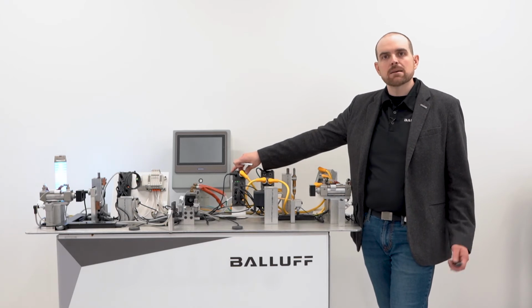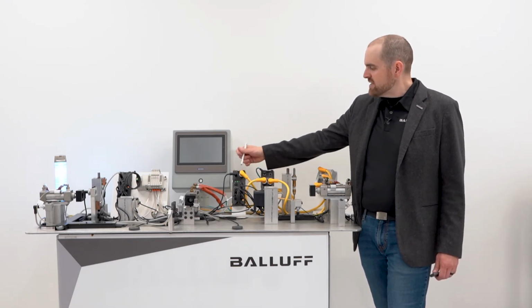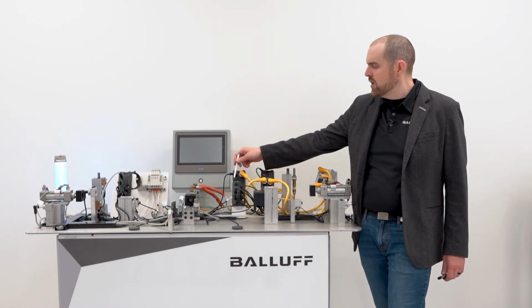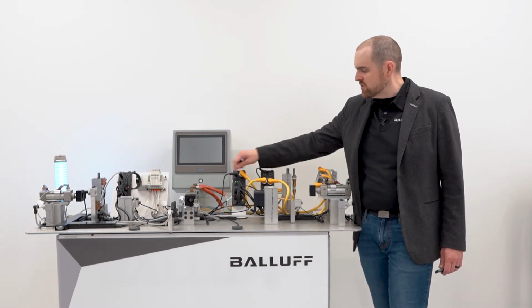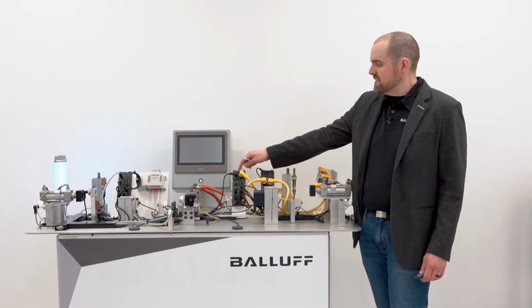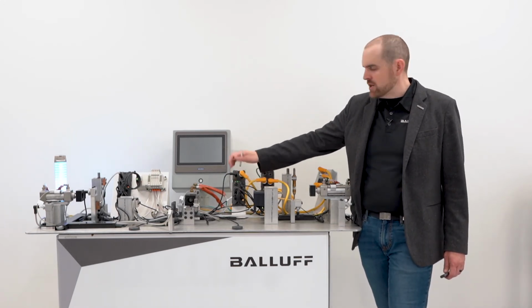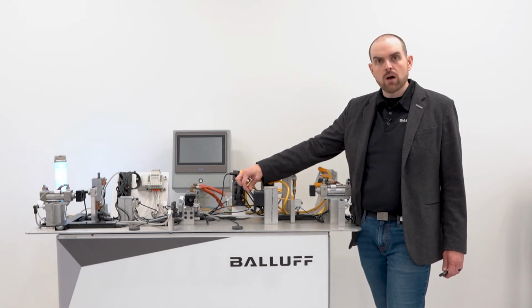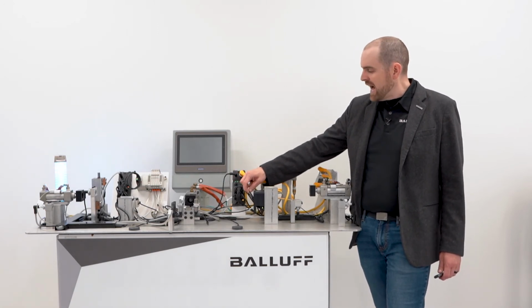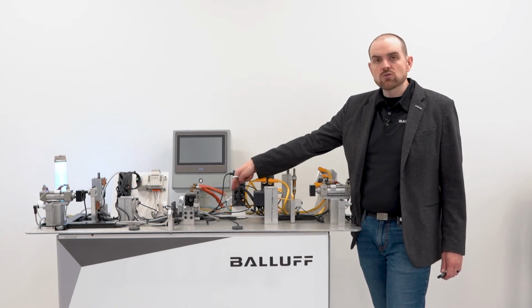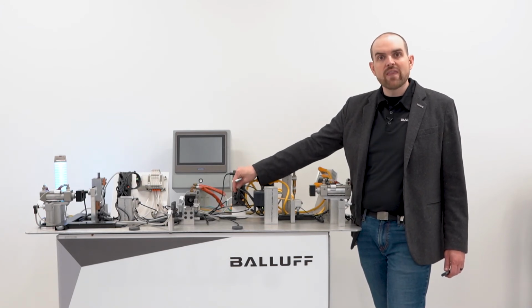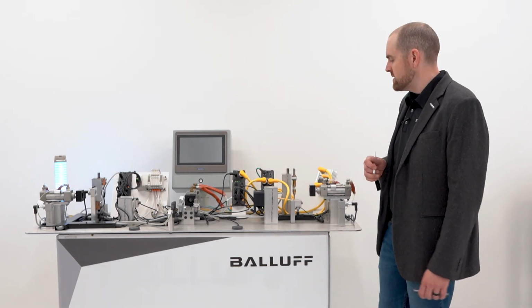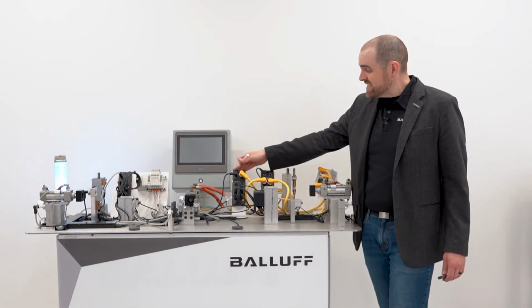So this is collecting basic sensor information. And the basic sensor information, just like an I/O block that you would have in a weld cell, is all collected together and sent over this standard sensor cable back to the master. What's nice about this is you can get diagnostic information, like you can get short circuits here, right? So if you get a short circuit from a weld spatter or a weld BB on the cable, you can actually diagnose that this exact cable is the one that has the short circuit. And so that allows you to change out faster and execute faster. So that's an I/O block.